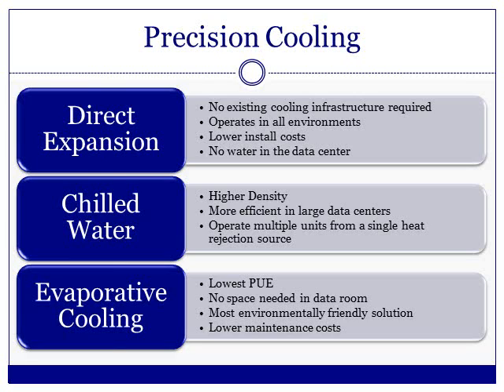Direct expansion cooling requires use of outdoor condensing units, typically installed on the facility rooftop or nearby open space on or above the same level as the data center. Direct expansion cooling is popular in part because it can operate in all environments and typically has lower installation costs. Both perimeter and in-row units are available in direct expansion models. Direct expansion cooling is seen as a good option for those IT and facilities professionals that are uneasy with the concept of chilled water in the data center.